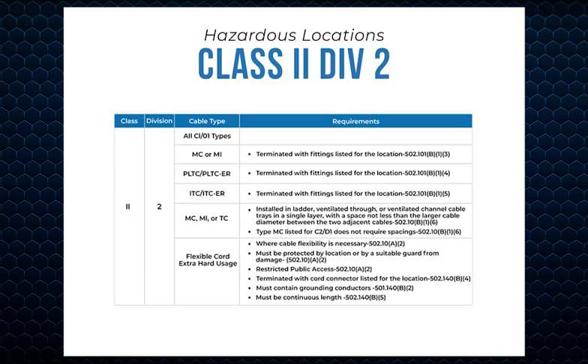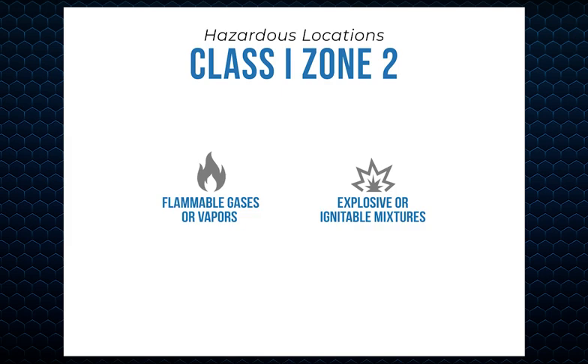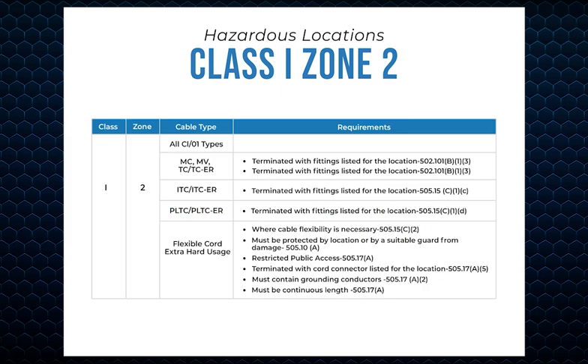Class 2 hazardous locations are areas in which combustible dust may be present in varying concentrations. Class 2 locations are further subdivided into 2 divisions. Class 1 locations are those in which flammable gases or vapors can be present in the air in quantities sufficient to produce explosive or ignitable mixtures. Class 1 locations are further subdivided into 2 divisions and 3 zones.